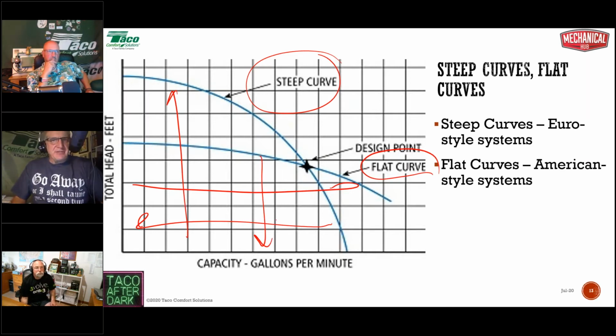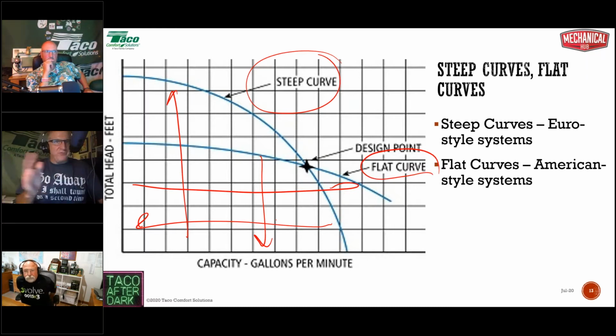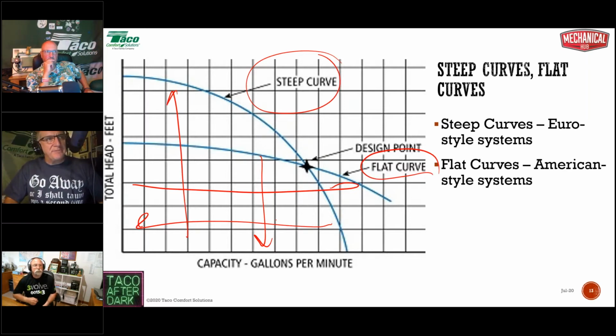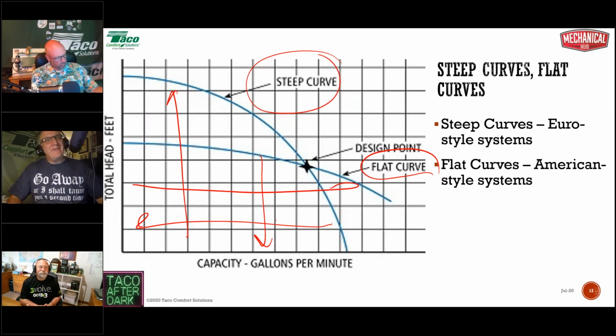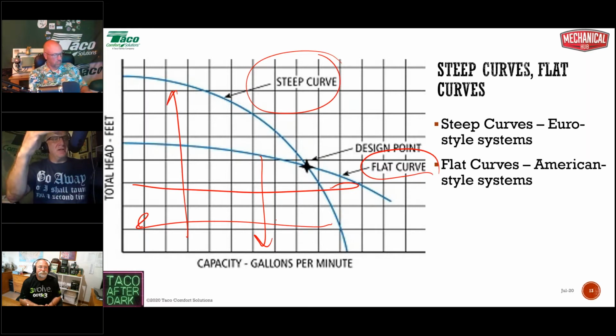In the world of pump manufacturing, steep curve pumps are known as European style curves, and they were designed for European style systems. We're talking panel radiators with small dimension pipes, small diameter PEX, and a home run to each radiator from a central manifold with a thermostatic radiator valve designed to a 40-degree delta T. All right, lower flow, a 40-degree delta. If I've got a 100,000 BTU boiler, all right, a 100,000 BTU system at a 20-degree delta T, that's 10 gallons a minute worth of flow rate. At a 40-degree delta T, that's 5 gallons a minute worth of flow rate. You run 5 gallons a minute, so lower flow, but you're running it through small pipe anyway, that's going to be higher head. Here in the US, we'll have higher flow, but we're going to run it through bigger pipe. It'll be a higher flow, lower head type of system.